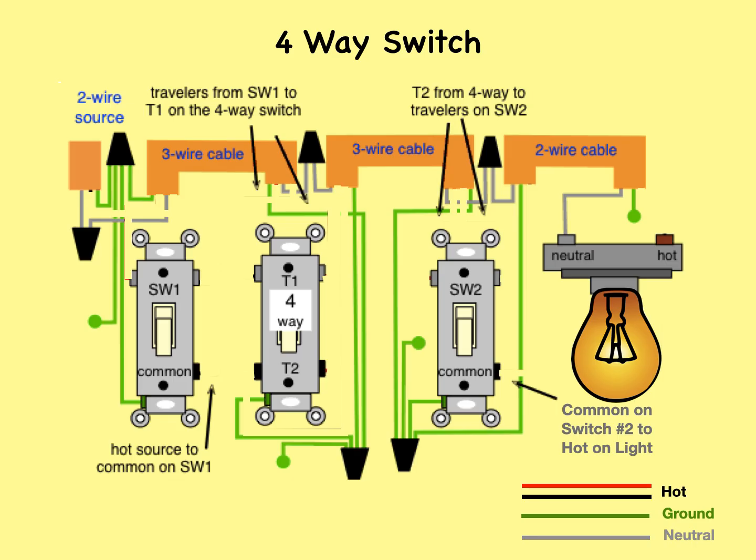In this basic four-way light circuit, three-wire cable runs between all the switches, and two-wire cable runs from the last switch to the light. The electrical source is at the first three-way switch, and the hot wire connects to the common there. The circuit neutral is spliced at each switch box through to the light fixture using the white wire.